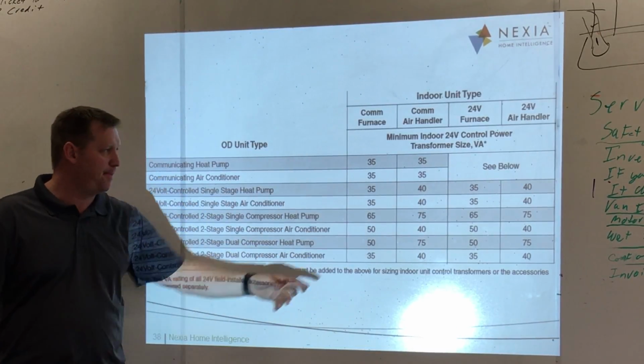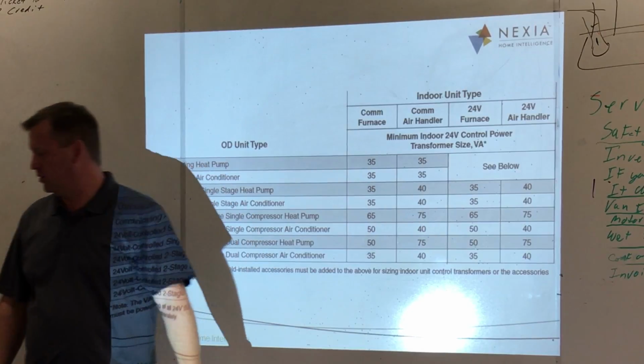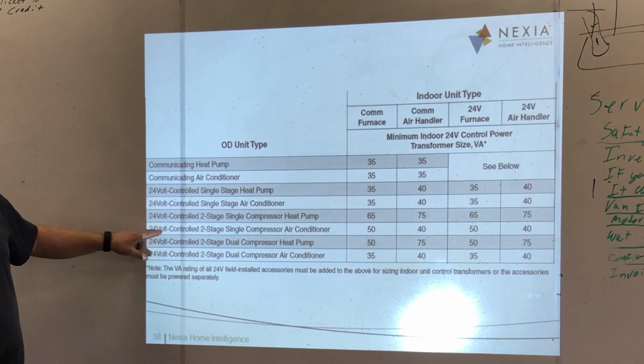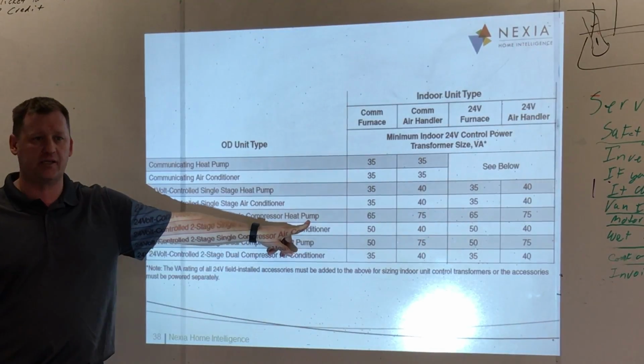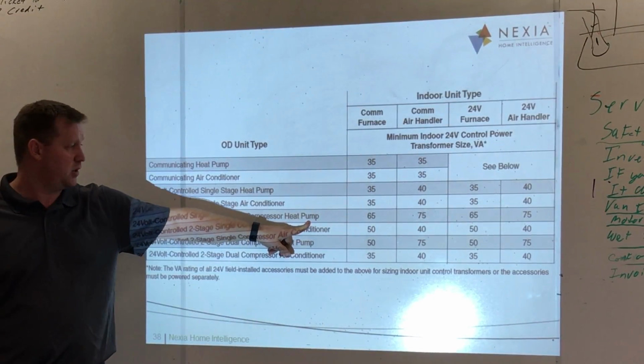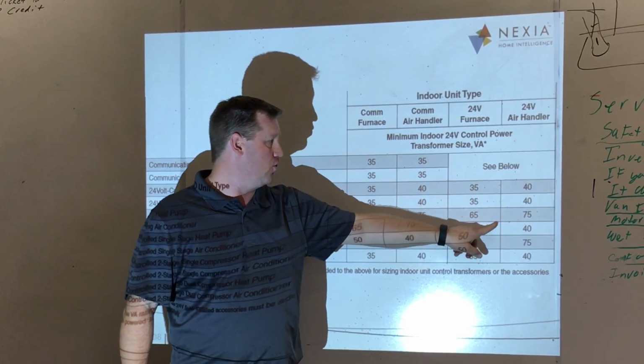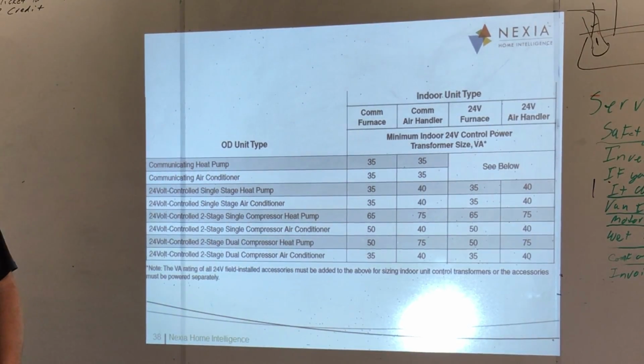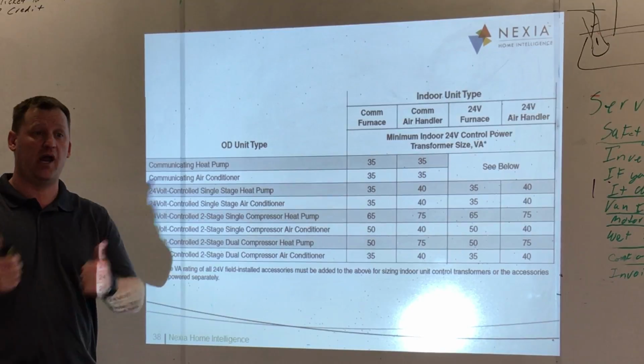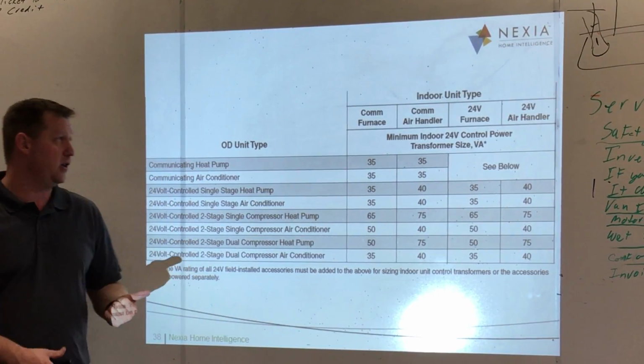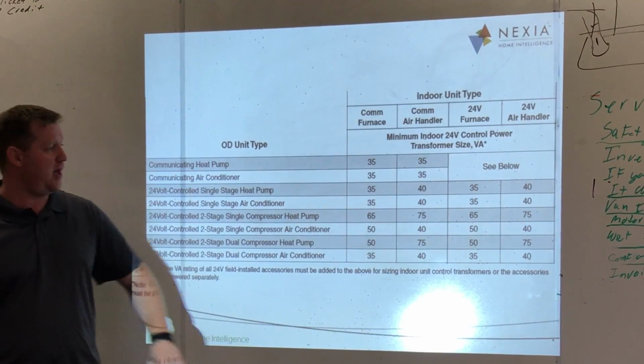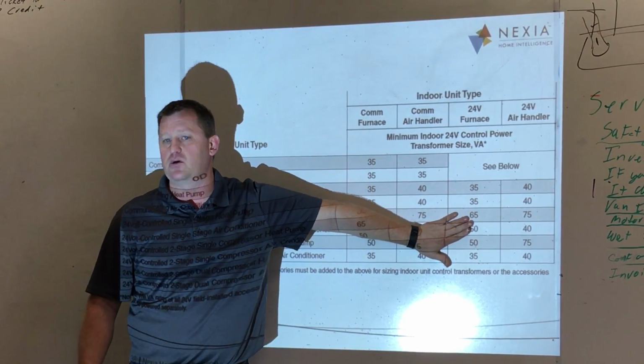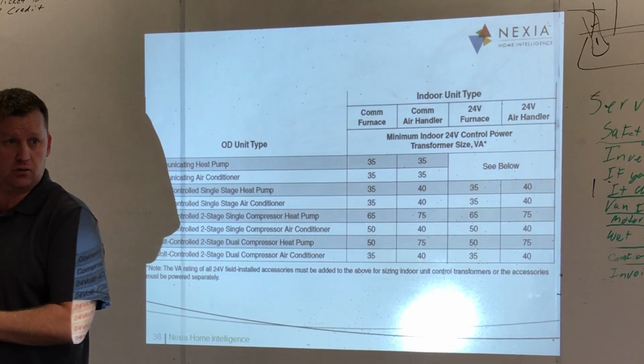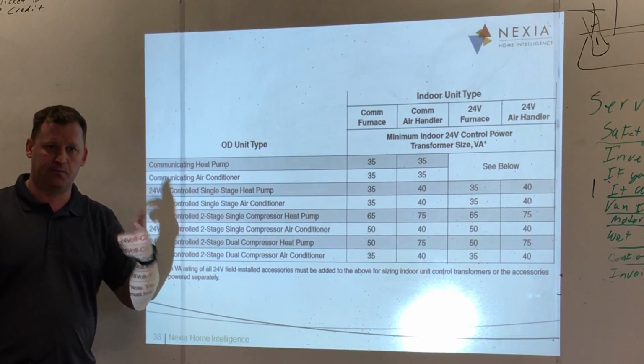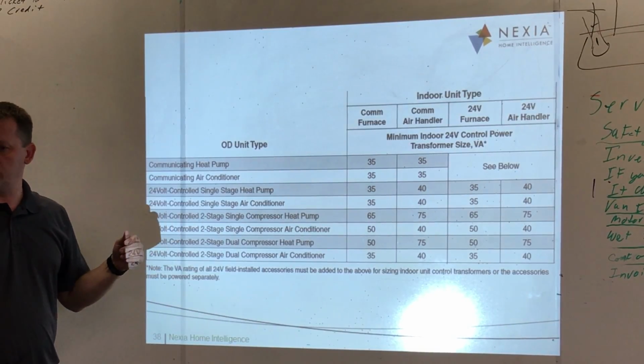When we do these units, you need to pay attention to the VA usage. All right, because if you've got a 2-stage single compressor heat pump, this is an XR17 or XL18, okay, with a 24 volt furnace or a 24 volt air handler, you need 65 or 75 VA respectively. Okay, so you could be in a situation where we're going to have to upsize the transformer. Now let's add that Clean Effects at 17 VA on top of this. Okay, we may need to power that Clean Effects separately. Okay, and I've got wiring diagrams. I believe I've sent them to Ken on those as well if we need to do that.